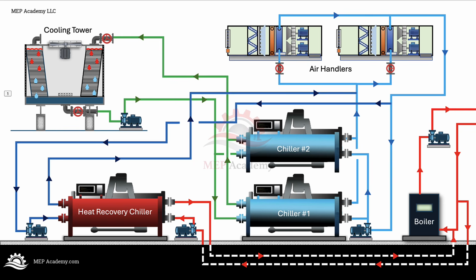Now let's talk about operation. Some heat recovery chiller systems operate in cooling priority. That means the chiller runs mainly to satisfy a chilled water load. If there is a useful heating load available, the system recovers heat. If there is no heating load available, the system may reject the excess heat through a tower, fluid cooler, or other heat rejection device. Other systems operate in heating priority.